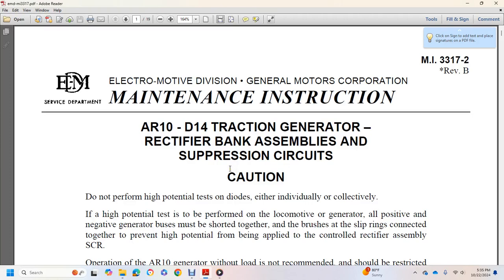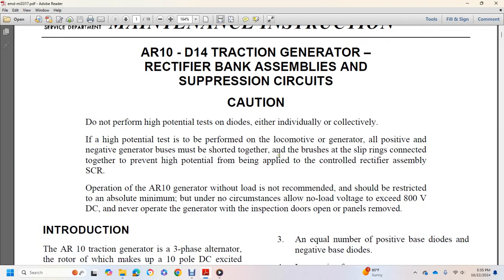Alright, Electro-Motive Division, General Motors Corporation, Maintenance Instruction 33.17.2, Revision B, AR10, D14 Traction Generator, Rectifier Bank Assembly, Suppression Circuits. Caution: do not perform high potential tests of the diodes, either individually or collectively. High potential tests of the generator: all positive and negative generator buses must be shorted together, with the brushes of the slip rings connected together, to prevent high potential from being applied to the controlled rectifier assembly.